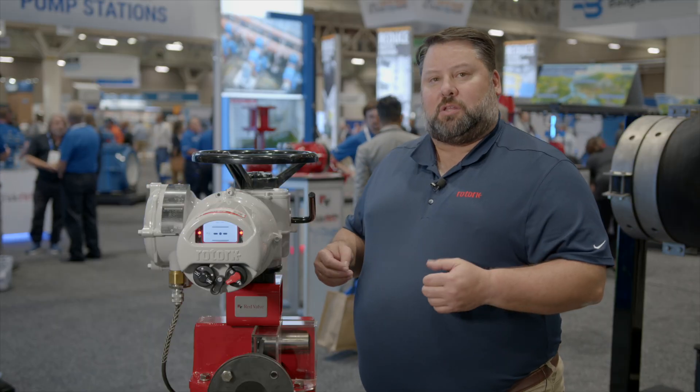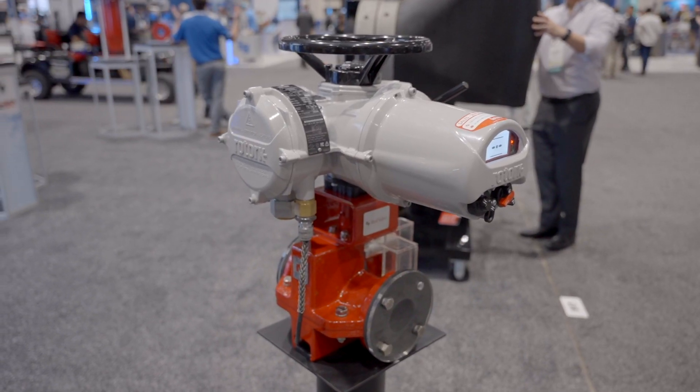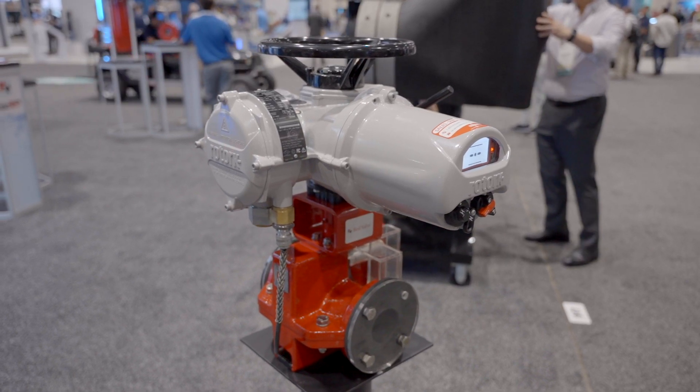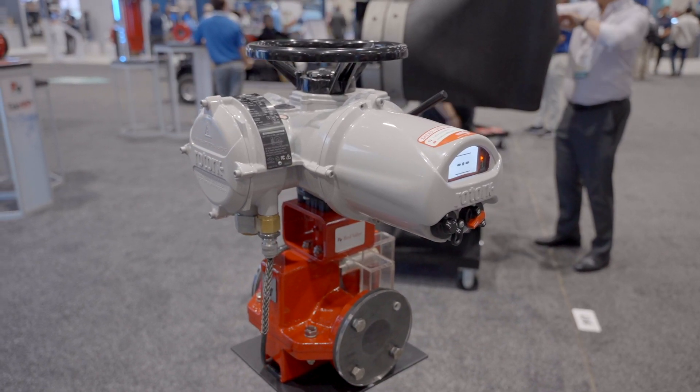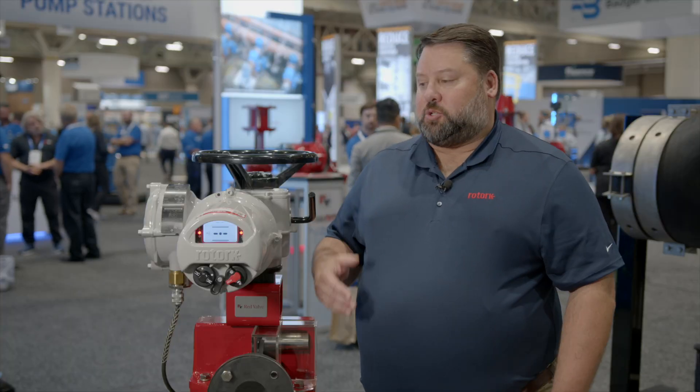What makes Rotork different is we use absolute encoders within the actuator. We have oil bath lubrication and a piezo sensor that monitors the constant thrust of the actuator for protection of your valve. This version of our IQ3 is our Pro version of the actuator, which is a new part of our actuator that just came out this last year. Our IQ3 Pro offers many new features that increase the reliability and the usage of the actuator.